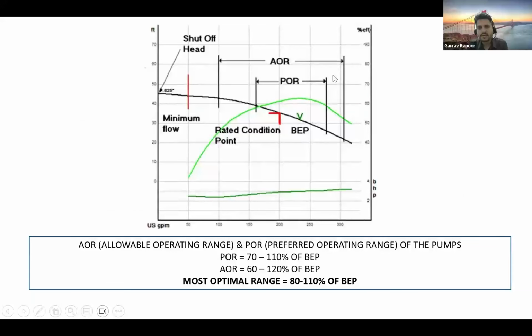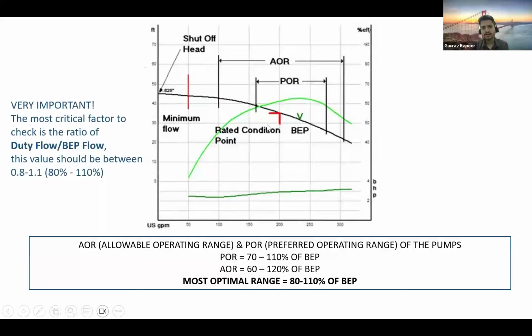Now this is a chart which we have pulled up from one of the standards, which talks about where you should select your duty point. Duty point is nothing but the flow and head required for your particular pump plant room. Let's say your duty point is this red arrow. It is recommended to always select this red arrow within the preferred operating range, which is 70 to 110% for any conventional system, meaning where you're using standalone chilled water for a building. But if you talk about DCS, it is very tight. It is recommended to have your duty point within 90 to 110% of the best efficiency point.